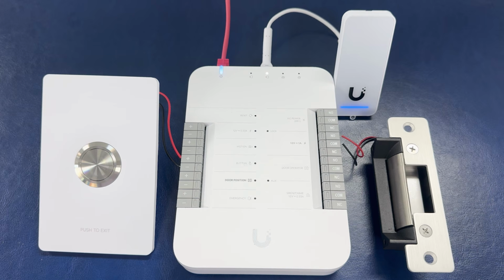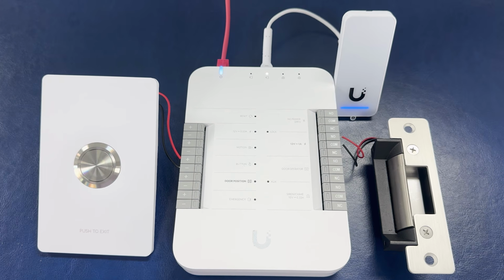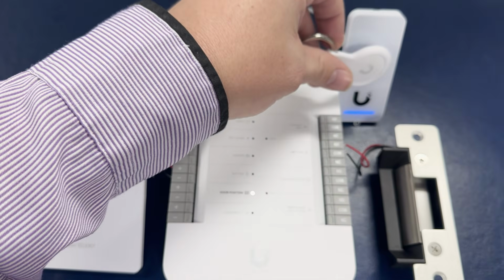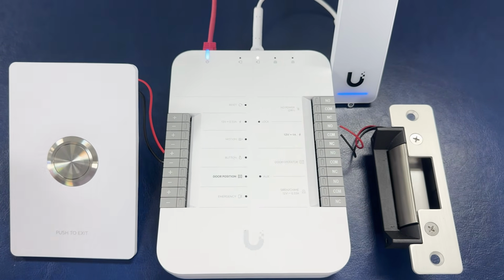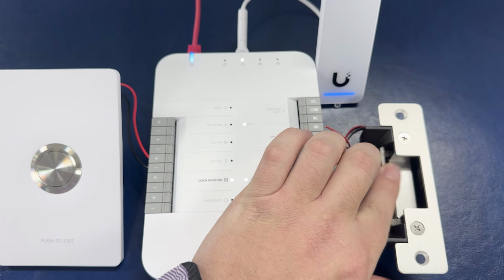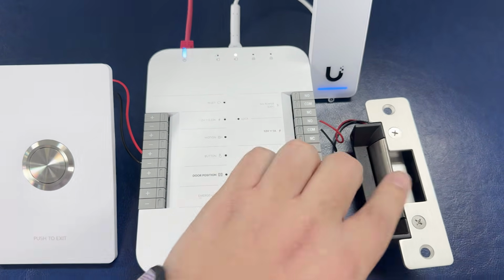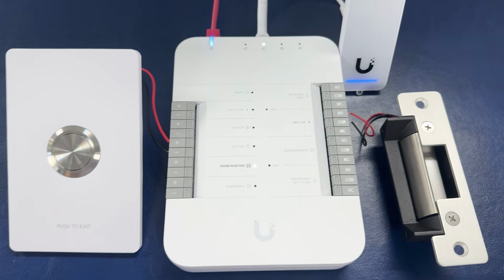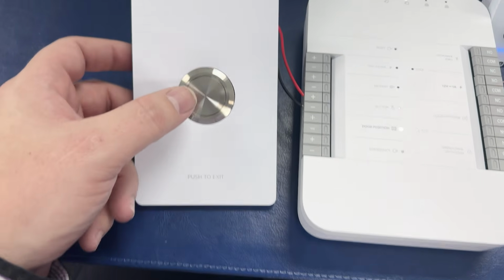Okay, so what we're going to do here is, firstly, connect our hub to Ethernet and get power from that. I'm also connecting up the G2 reader or the G3 reader. This is the regular version that doesn't have the built-in camera. You'll see I've also got a lock and a push button attached to this. The concept being that the lock would obviously be in a door frame, and you would do the authentication via key fob to allow the door to unlock. You'll see me in a second push the lock in, and you'll see that triggering. The push button is obviously just a push button exit, and you can push the button to open the door.